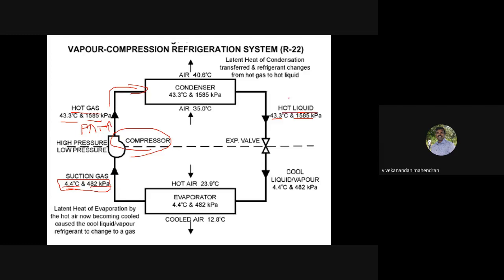Now the most important thing is the expansion valve, what we studied previously. It comes with high pressure. The expansion valve has a tube diameter of 6 mm. It's a small device, more like a spring, which you can see at the back of your fridge — a small spring with an orifice where the diameter is very small, going from 6 mm dia to 0.6 mm dia.